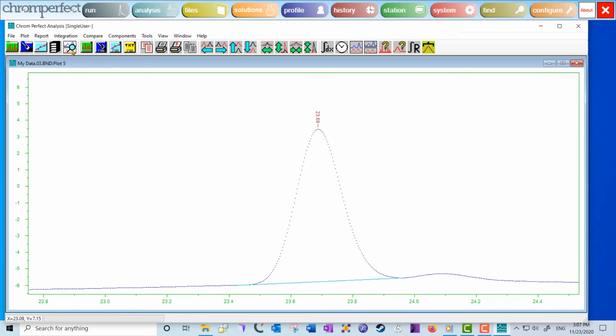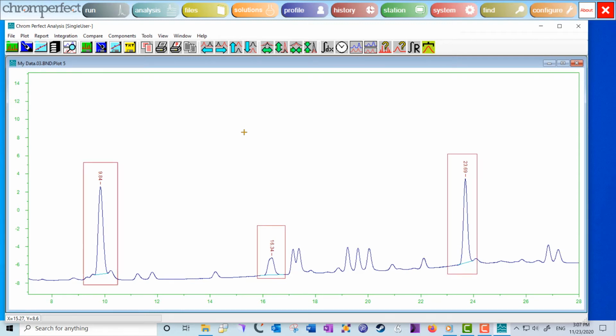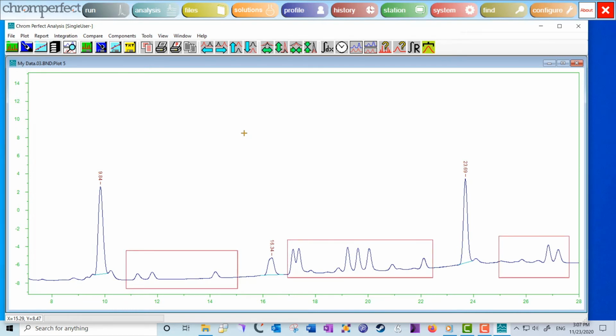Let's move on to some other things that should be considered. The example illustrates a problem that frequently appears even when the sampling rate is adequate. Not all the peaks have baselines. In this case, only 3 peaks were recognized. This indicates that the integration parameters, the threshold and the peak width, are not optimum. The proper values must be chosen by the user, but there are tools which will suggest appropriate values. As we improve these parameters, more baselines will appear, and more peaks will become decorated with retention times.